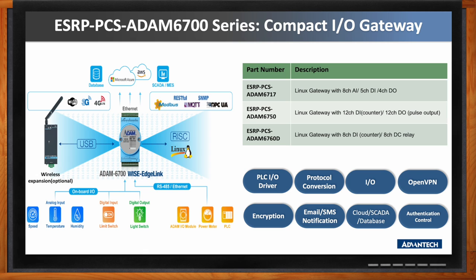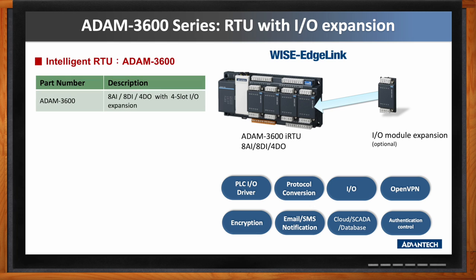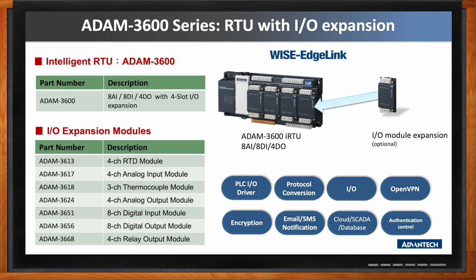You also mentioned the ADAM-3600. Can we take a closer look at that one? The ADAM-3600 is similar to the ADAM-6700 series, but the key difference is that it has I/O expansion. By default, the ADAM-3600 comes with eight analog inputs, eight digital inputs, and four digital outputs. Users can add more I/O expansion modules for different I/O needs in applications. For centralized systems with higher I/O count demands, ADAM-3600 is a good fit. For distributed systems, the ESRP ADAM-6700 series is more suitable. The ADAM-3600 has one RS-232 port, one RS-485 port, and two Ethernet ports, and also supports wireless communication with wireless accessories.